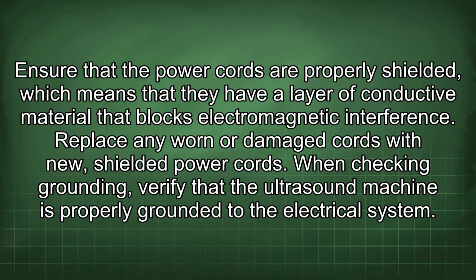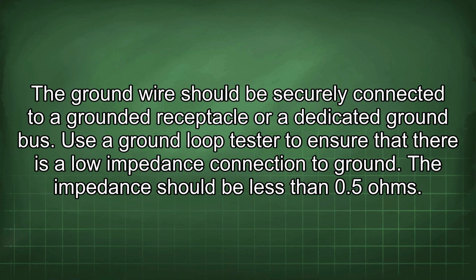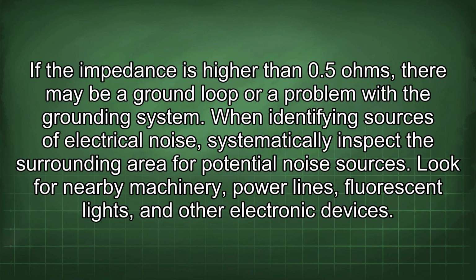When checking grounding, verify that the ultrasound machine is properly grounded to the electrical system. The ground wire should be securely connected to a grounded receptacle or a dedicated ground bus. Use a ground loop tester to ensure that there is a low impedance connection to ground. The impedance should be less than 0.5 ohms. If the impedance is higher than 0.5 ohms, there may be a ground loop or a problem with the grounding system.